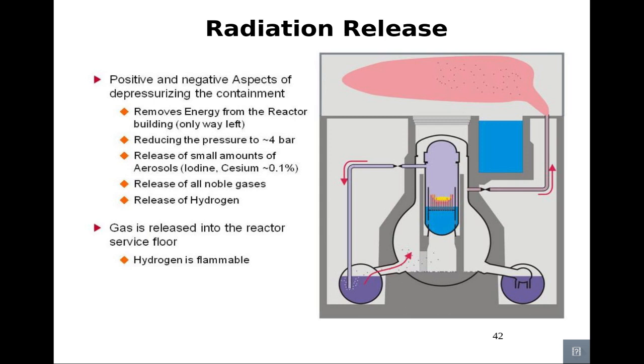There are both positive and negative effects of depressurizing containment. The positive effects are to reduce the pressure in containment to below design basis and allow water injection. The negatives are releasing a small amount of aerosols, which include iodine and cesium, the release of all noble gases, and a release of hydrogen, which really could be good and bad. You don't want the hydrogen in containment to explode, but it releases hydrogen into the service floor where it can explode there.